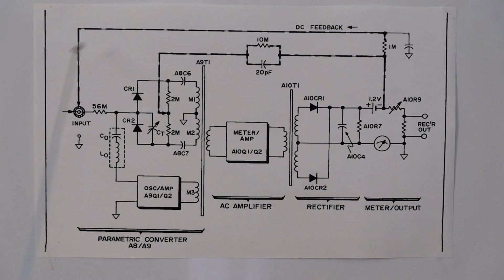Now the practical use of this instrument, of course, is that unless you have the right probes and the right technique to measure such high resistances, you're probably going to get incorrect results if you don't do it correctly. You need to have extremely good cables and shielding and so on. I don't have the correct cable for this one, but I'm never going to be measuring above 10 to the 12 at the most, in my limited use of this instrument, but it can of course measure several orders higher than that, so it's definitely capable of that, like a real mega instrument.